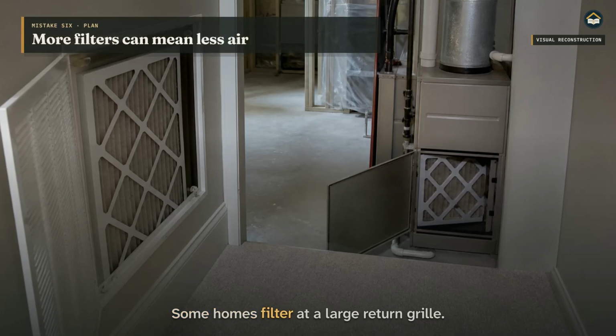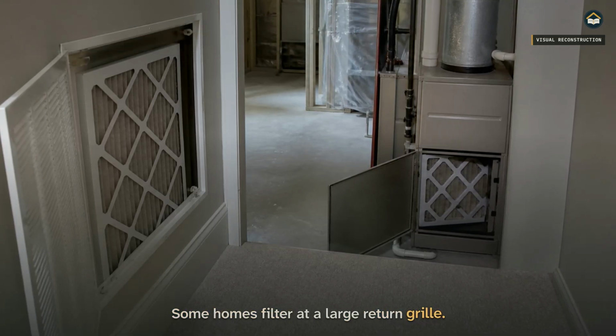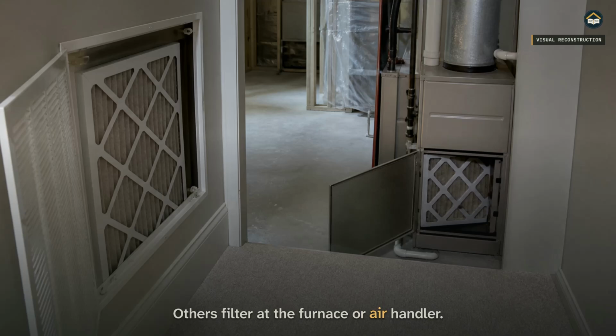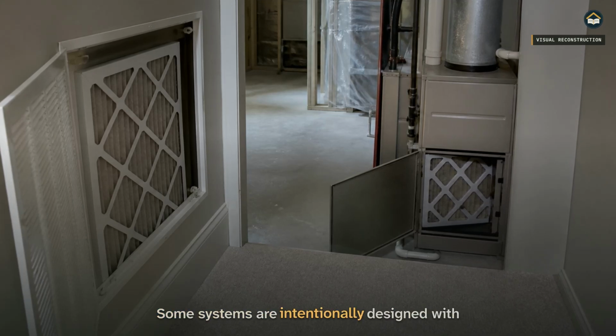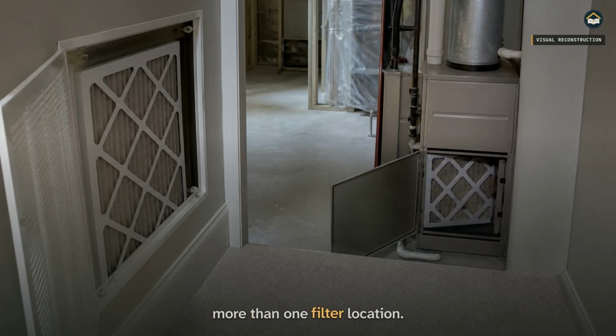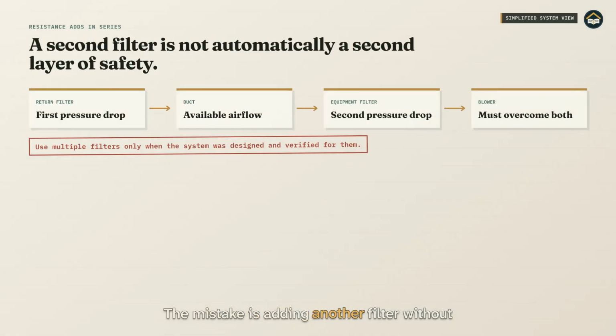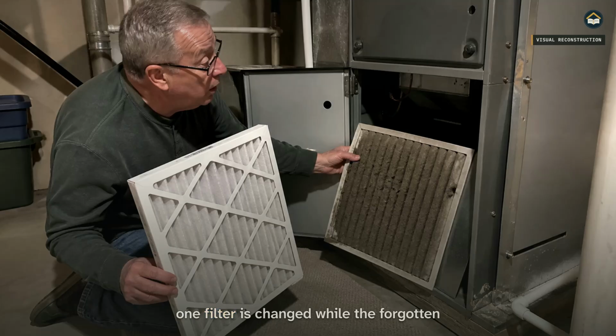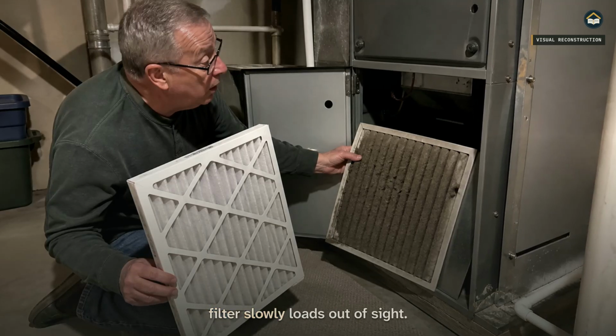Some homes filter at a large return grille. Others filter at the furnace or air handler. Some systems are intentionally designed with more than one filter location. The mistake is adding another filter without knowing which arrangement the system expects. Every filter adds some resistance. A return grille filter plus another filter at the equipment can reduce airflow if the blower and duct system were not designed for both. It can also create a maintenance trap. One filter is changed while the forgotten filter slowly loads out of sight.